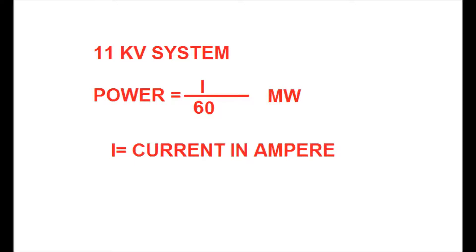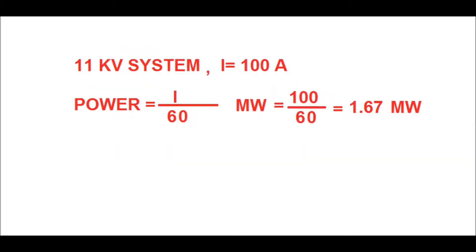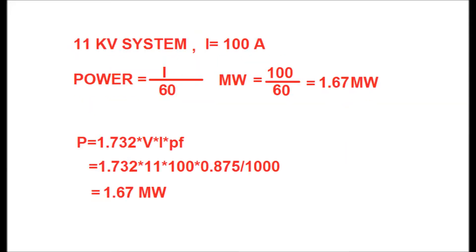Therefore, for an 11 kV system, if current is 100 amperes, then you will get the value of power in megawatts as 100 divided by 60, equal to 1.67 megawatts. Now, how does this factor of 60 come?